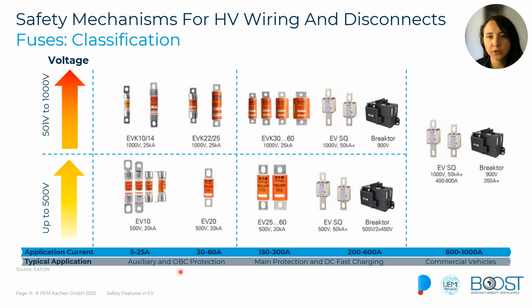These fuses have lower amperage, often between 5 and 25 amperes or between 30 and 60 amperes, and they are used in the peripheral components operating in the battery system, from a few volts to 1000 volts depending on the system. Besides these auxiliary systems, we can also have fuses in the main protection path and in the DC fast charging. These mid-range fuses will typically handle voltages between 500 and 1000 volts, and the current can go up to 600 amps depending on the architecture of the vehicle. And finally, we can also have some larger fuses that can go up to 1000 amperes that are used, for instance, in heavy duty and high capacity battery packs.